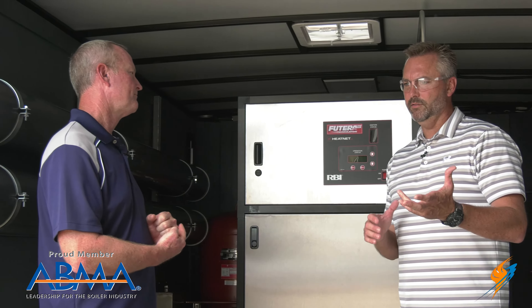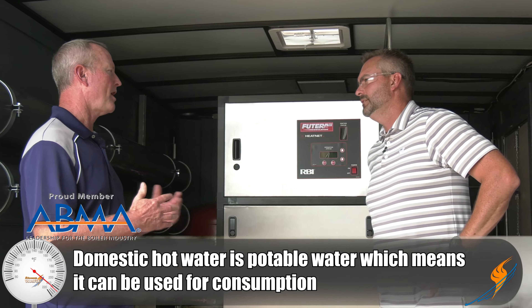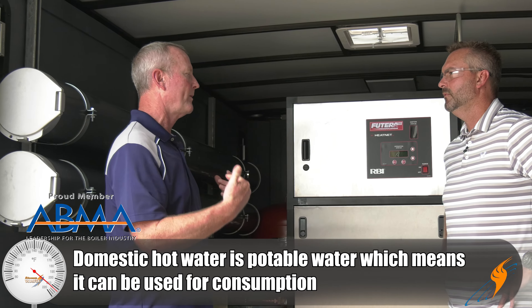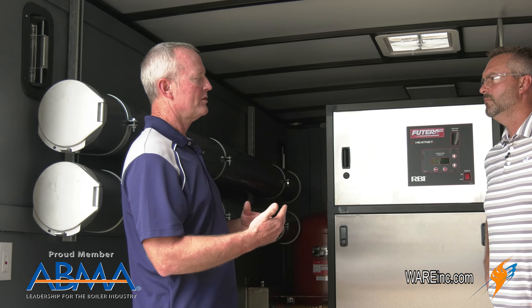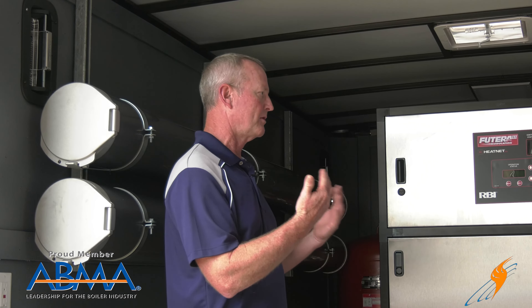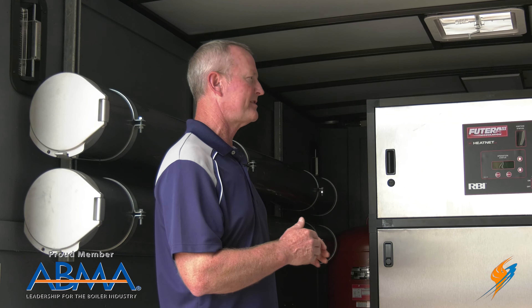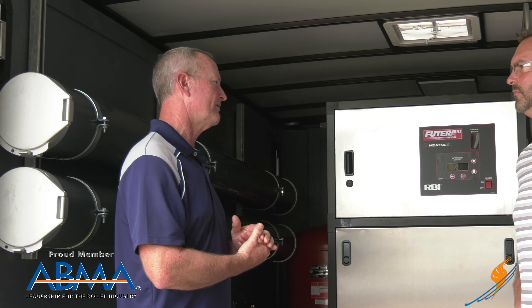I hear people talk about domestic hot water — what actually is that? Domestic hot water is potable water; that's water that you and I can drink, that we take a shower with. That's domestic. For heating hot water, you can use cast iron and steel. But domestic hot water — something that's food grade or that we'll personally come in contact with — has to be all copper or all stainless steel. There can't be any iron in there that's going to rust and cause problems down the road.